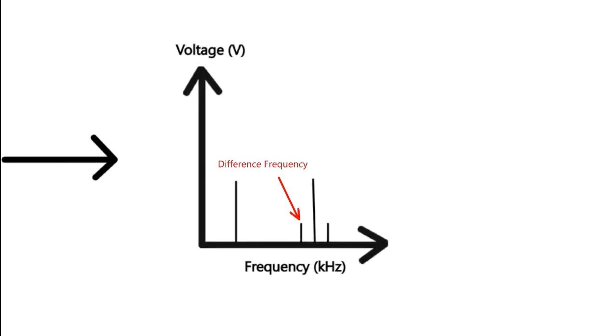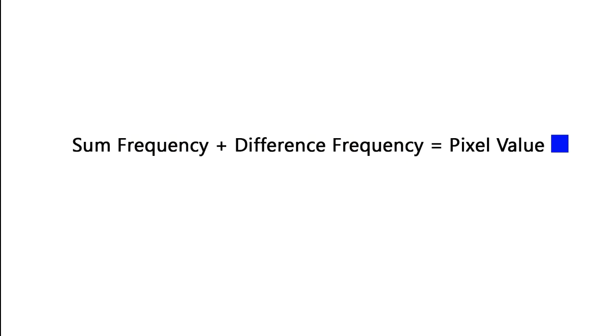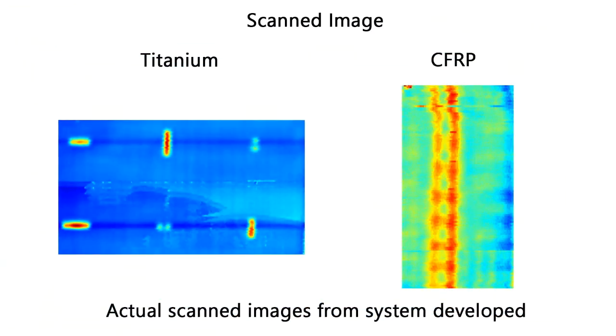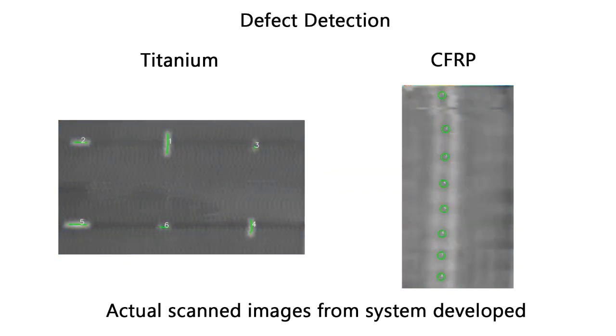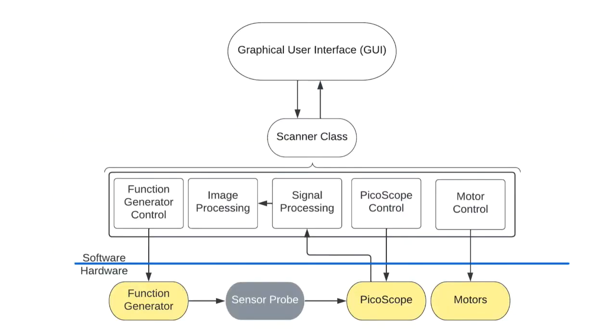A fast Fourier transform is then applied to each discrete block in order to extract the values of secondary magnetic field, which exist at specific frequencies in the signal, known as the sum and difference frequencies. These values are then combined to derive the intensity level of the corresponding pixel. The pixels are then finally combined in order to form a complete image of the material. Our custom image processing software then translates the output of the signal processing into an interpretable image to the user, including showing the location and size of any defects present.